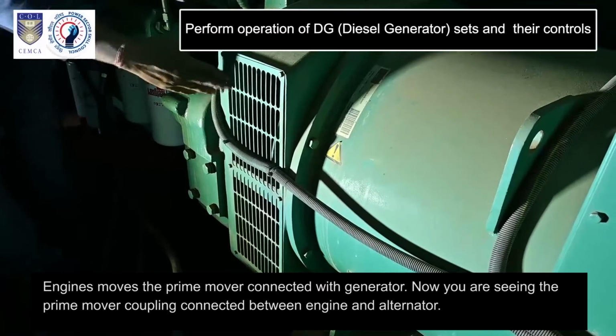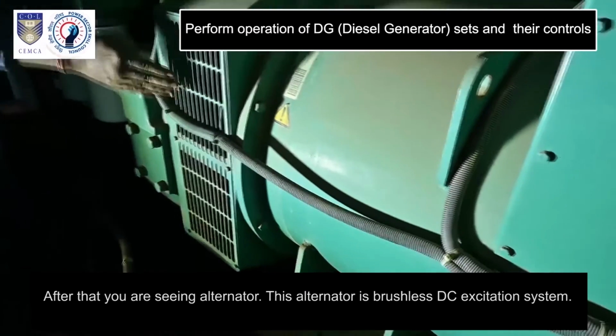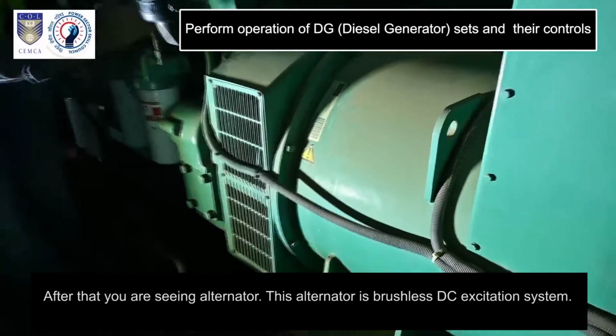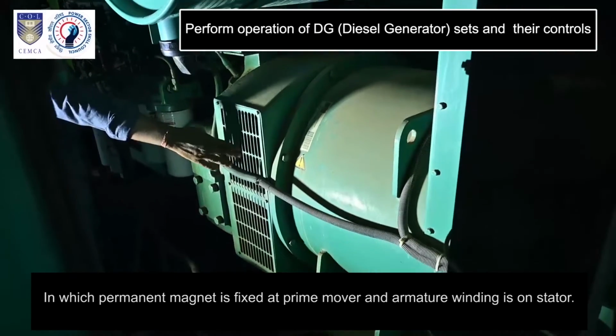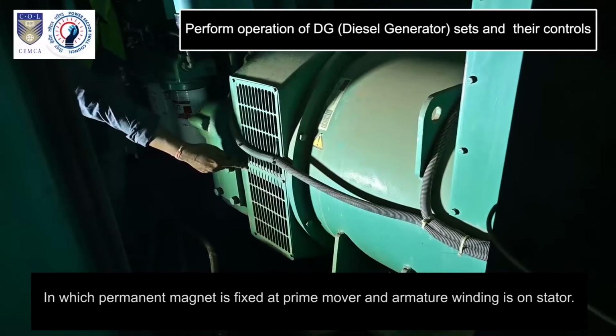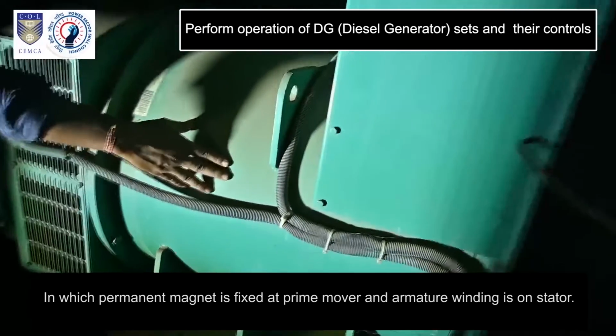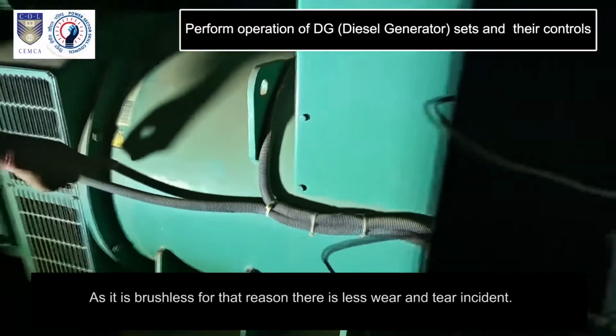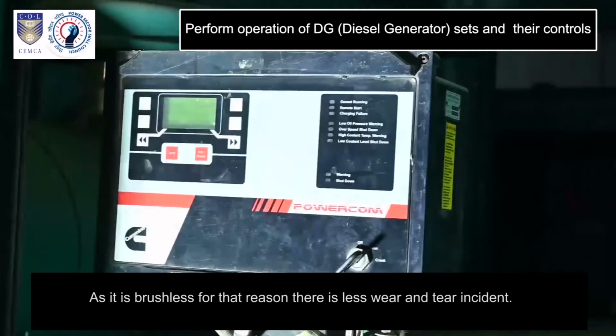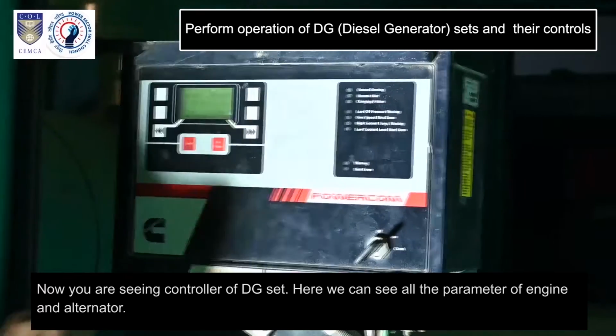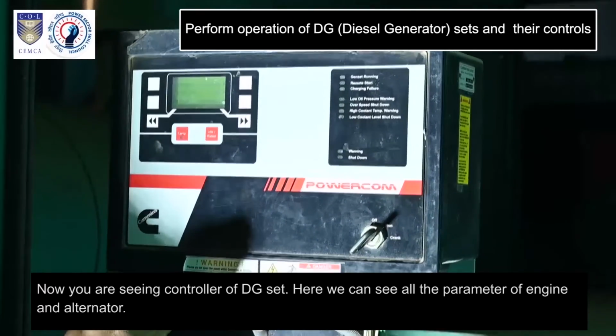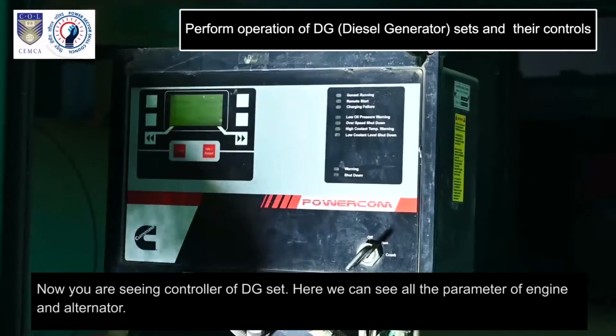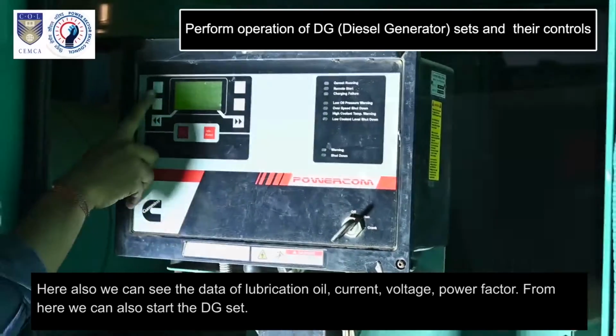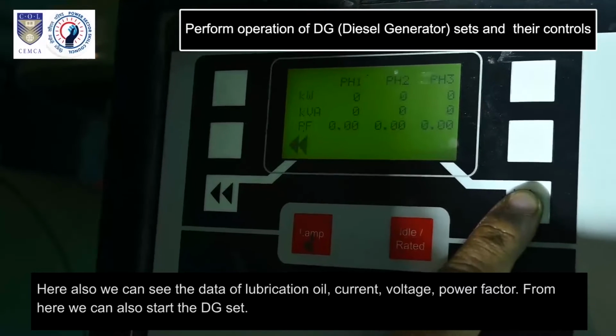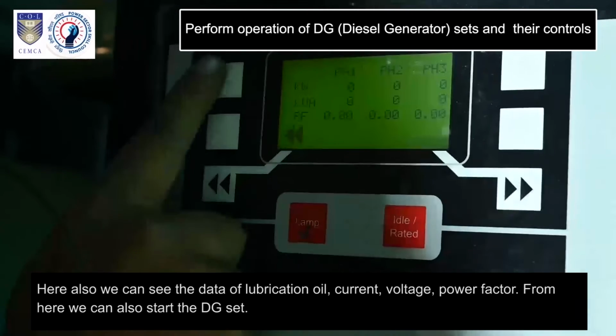Now you are seeing the prime mover coupling connected between the engine and alternator. After that you are seeing the alternator. This alternator is a brushless DC excitation system, in which a permanent magnet is fixed at the prime mover and armature winding is on the stator. As it is brushless, there is less wear and tear. Now you are seeing the controller of the DG set. Here we can see all the parameters of engine and alternator. Here we can also see the data of lubrication oil, current, voltage, power factor. From here we can also start the DG set.